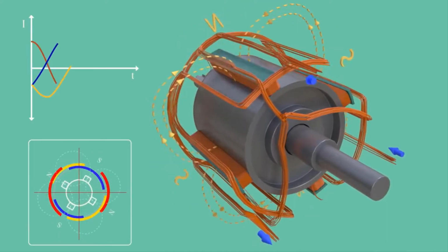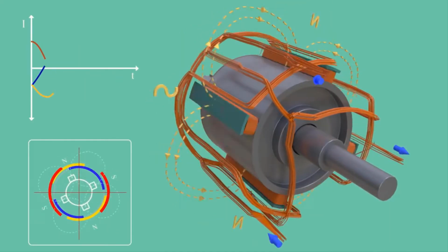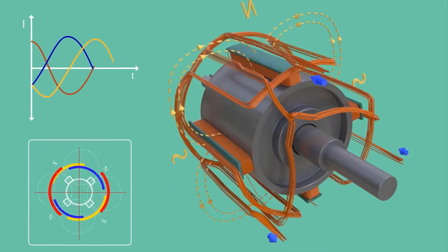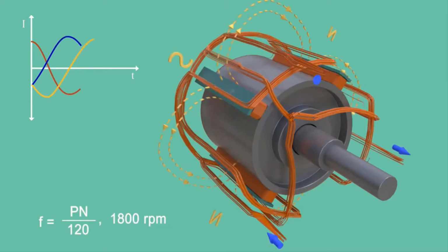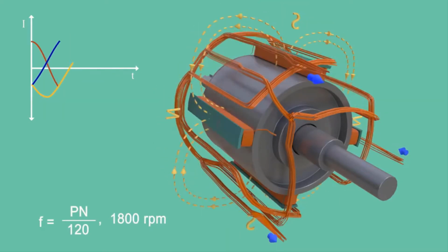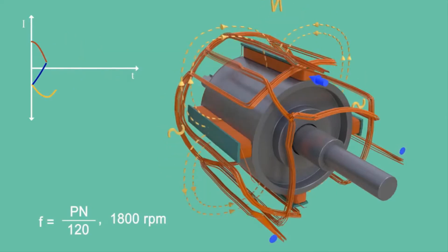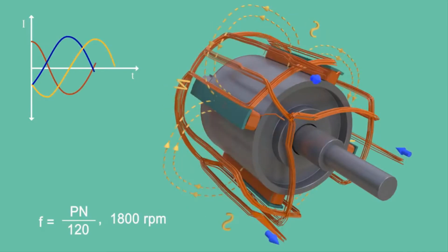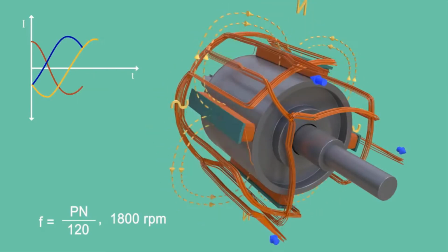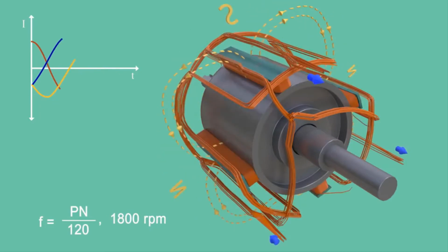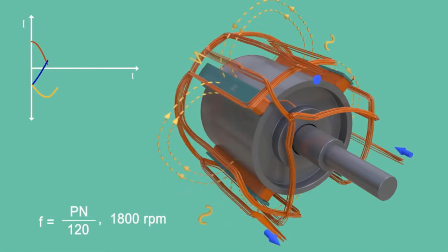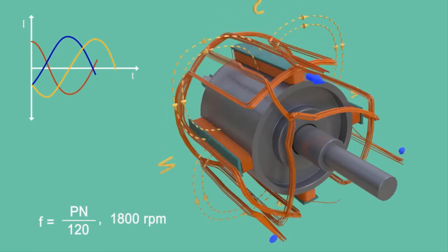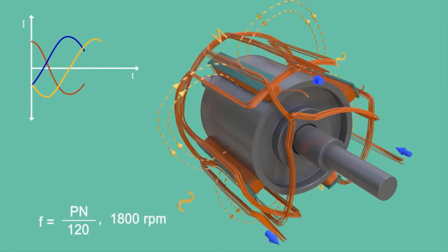It is clear from the past equation that in order to produce 60 Hz electricity, a 4-pole rotor should run at the following speed of 1800 RPM. Such huge RPM will induce a tremendous centrifugal force on the poles of the rotor and it may fail mechanically over time. So salient pole rotors generally have 10 to 40 poles, which demands lower RPM. Salient pole rotors are used when the prime mover rotates at relatively lower speed, from 120 to 400 RPM.